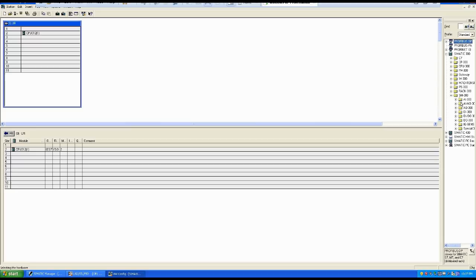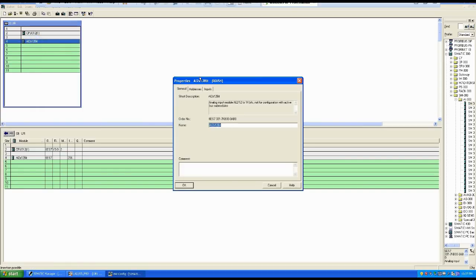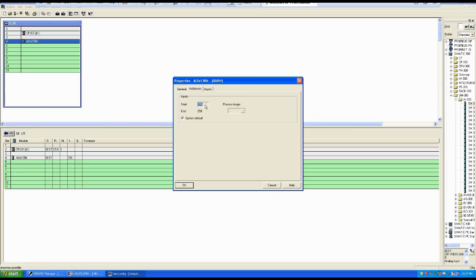We will not talk about the gateway today — we will just take the AI module. I take the AI from here and place it in the rack. Now remember you have to check the address range: starting from 256 and ending at 259. That card has that many addresses, so when selecting a channel from that card remember to use addresses within that range, otherwise you will get an issue.